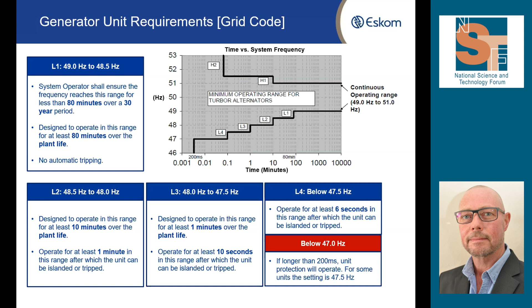And so you can see that if we get into a situation where we don't have enough capacity to supply the demand, and the frequency starts dropping, we will get into these ranges, and we will start to see generators automatically tripping off to protect themselves. Obviously, that then becomes a cascading problem. As more generators trip off, there is less capacity available to supply the demand. The frequency drops again, and so on and so forth. And you get into this cascading situation where you would eventually trip every generator connected to the power system.